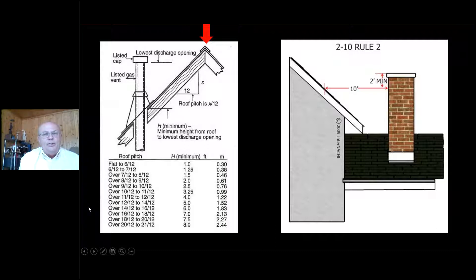Looking at the drawing to the left, you can see a red area pointed at the peak of the house, where the attic is vented — which is very common now. If the attic is vented and it is taller than the top of the chimney stack, we could have an issue with performance. And if there's an issue in performance, this is the problem you own from that point.